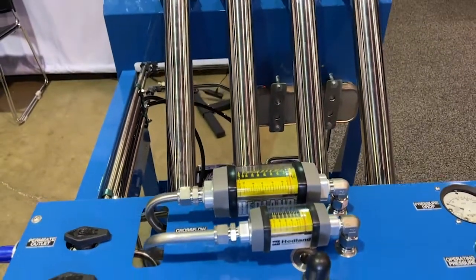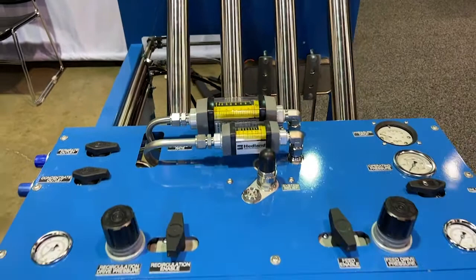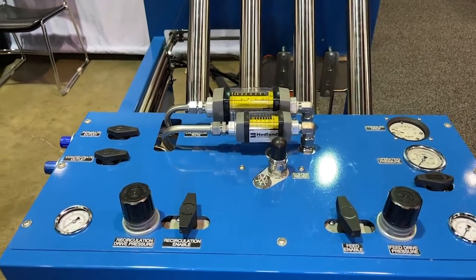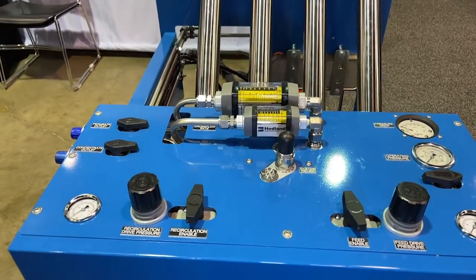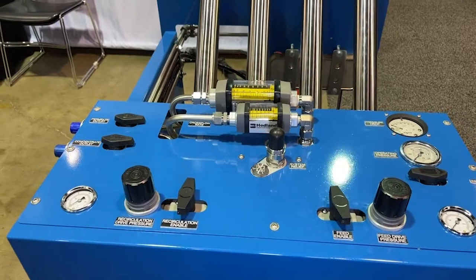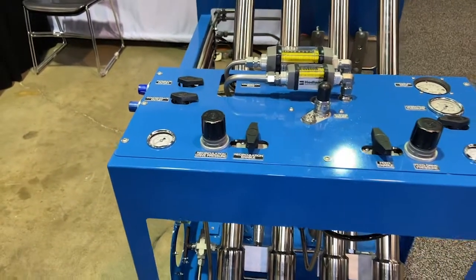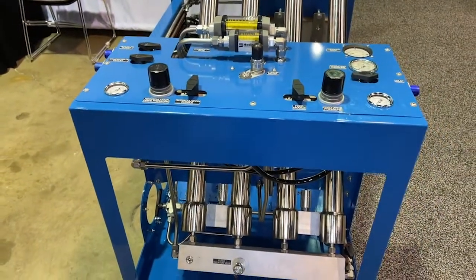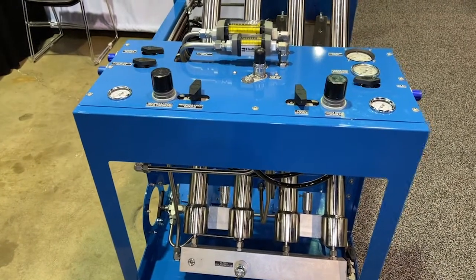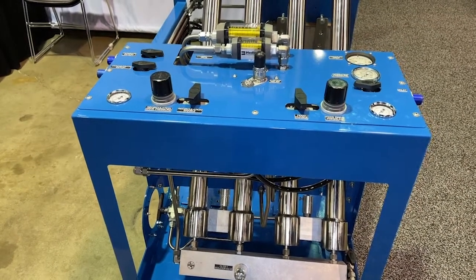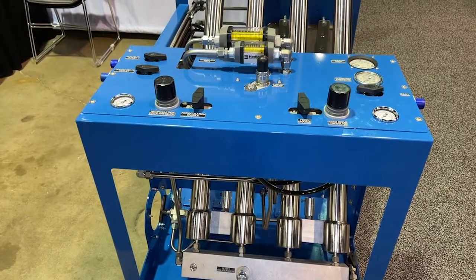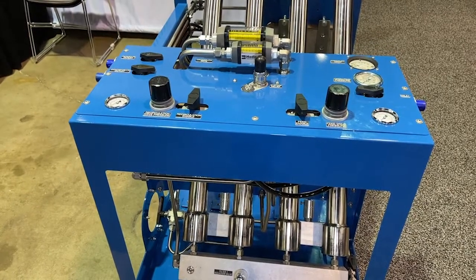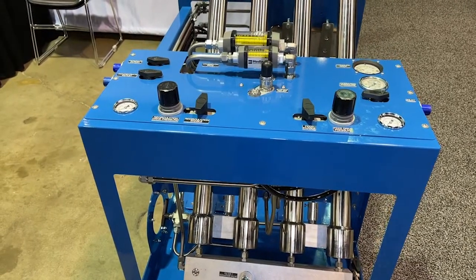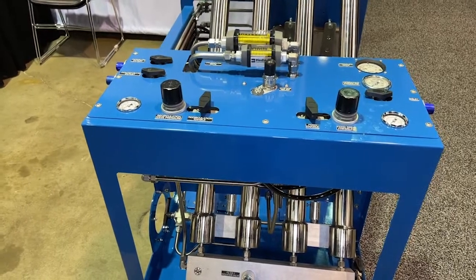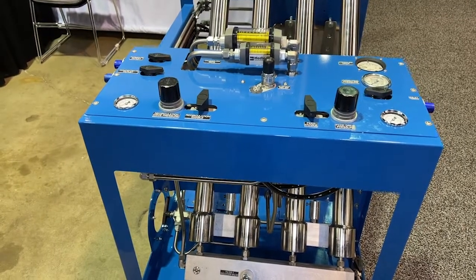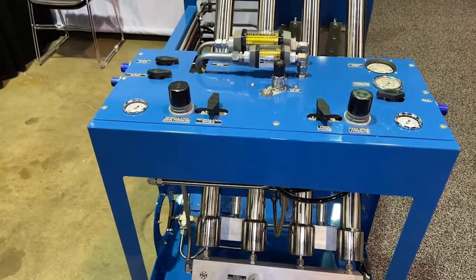But with this type of crossflow filter, you can adjust your crossflow, you can adjust your feed, all those things relatively simply in a C1D1 environment without fear of any kind of explosion or whatnot, because these are completely pneumatic. Again, they don't use any electricity. The crossflow is a completely sealed system. You don't need to input any secondary fluid to perform that self-cleaning function, and the self-cleaning function is continuous.